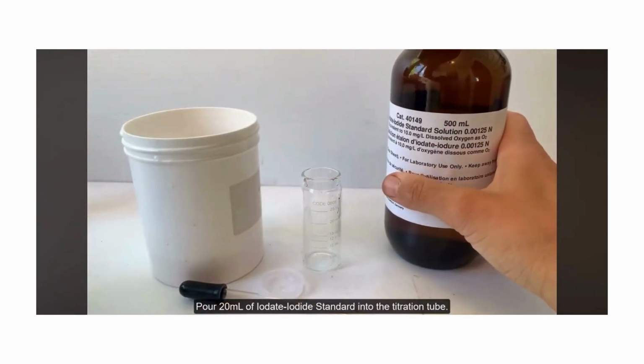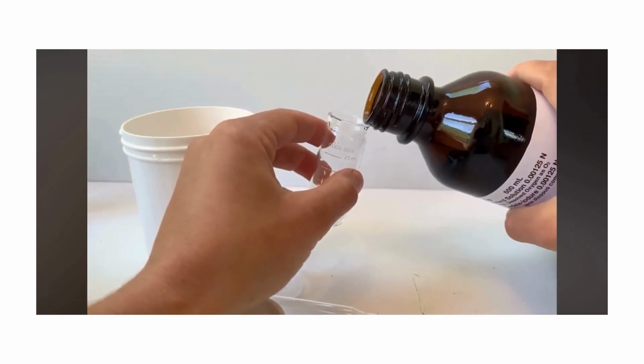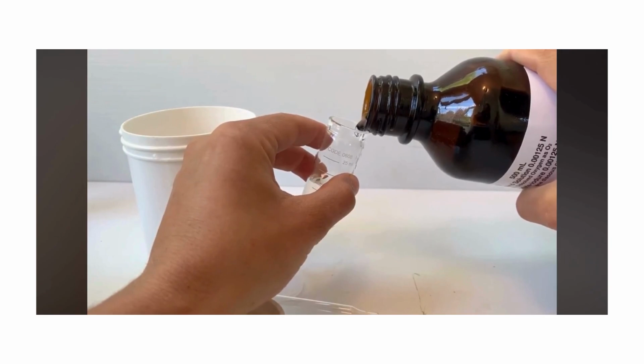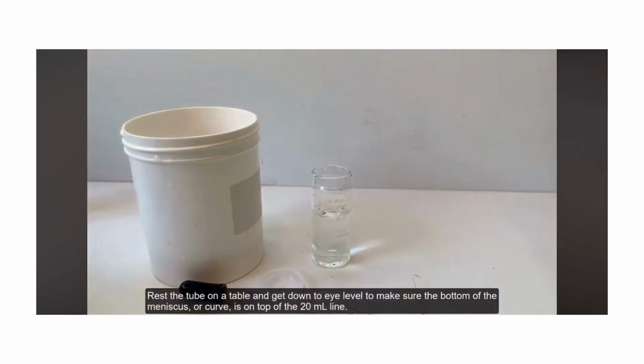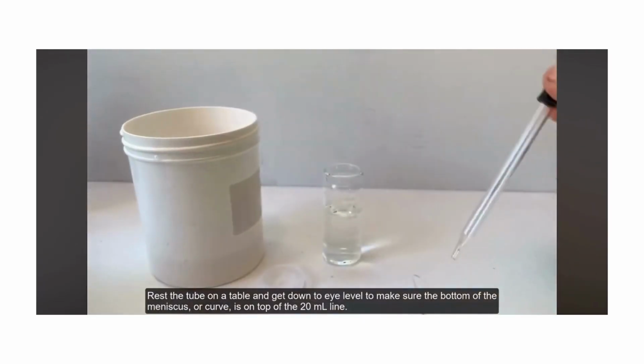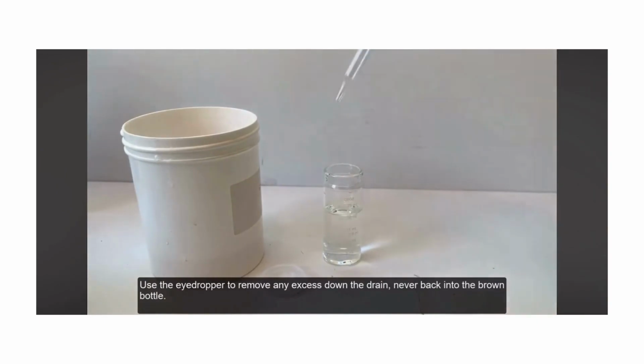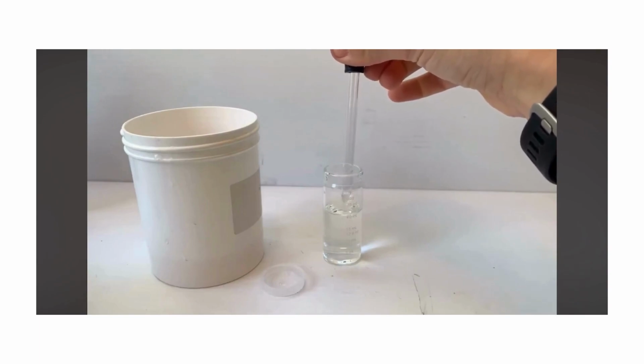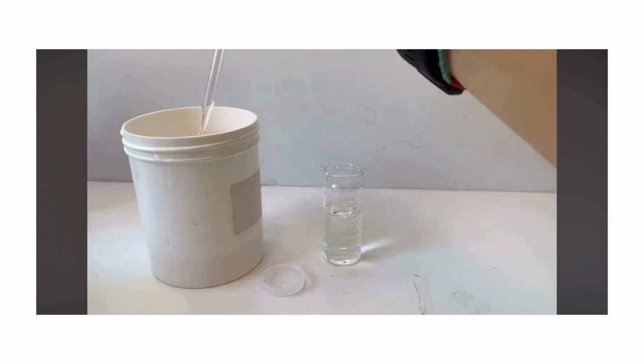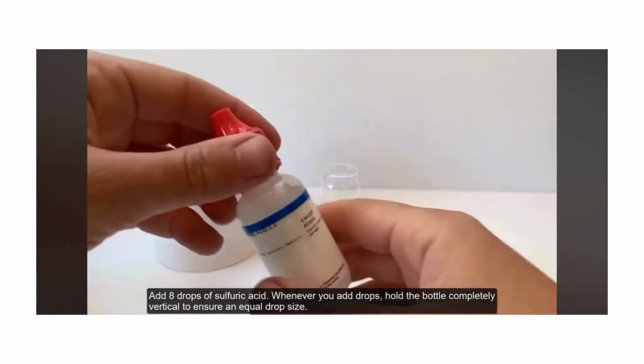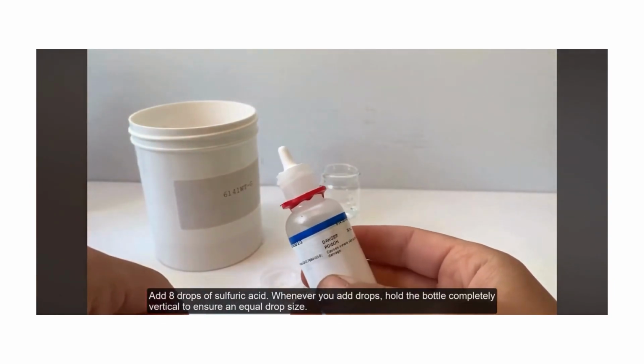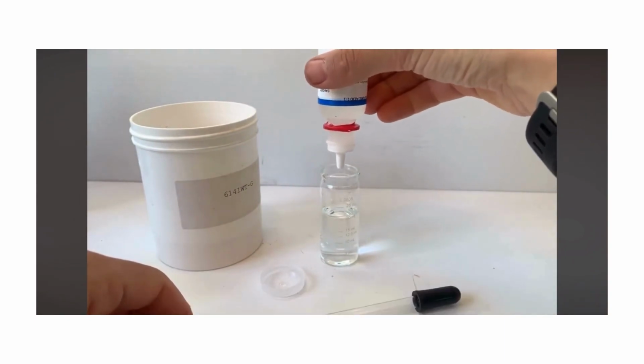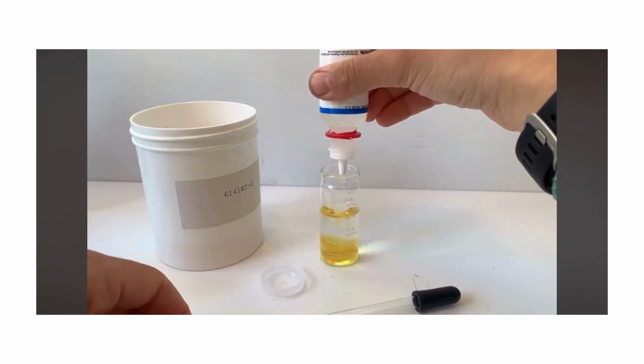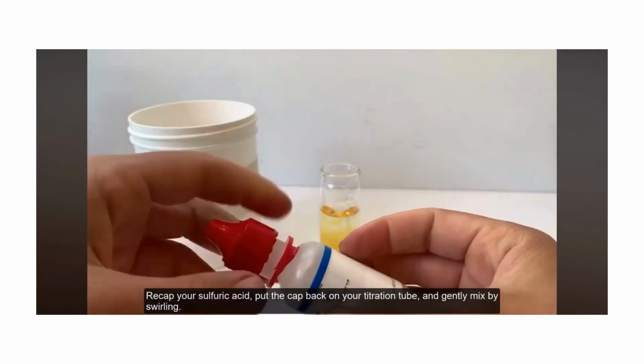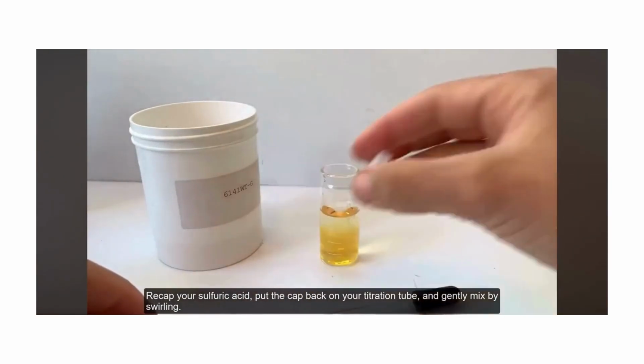Pour 20 mL of iodate iodide standard into the titration tube. Rest the tube on a table and get down to eye level to make sure the bottom of the meniscus or curve is on top of the 20 ml line. Use the eyedropper to remove any excess down the drain, never back into the brown bottle. Add 8 drops of sulfuric acid. Whenever you add drops, be sure to hold the bottle completely vertical to ensure an equal drop size. Recap your sulfuric acid, put the cap back on your titration tube, and gently mix by swirling.